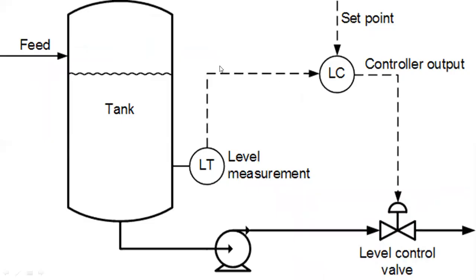For level control, the feed tank has a level transducer that measures the level and sends the signal to a level controller, which compares it with the set point. The controller output is sent to a level control valve. When the level drops, the pump output is reduced so that the tank always maintains a certain level corresponding to the set point.